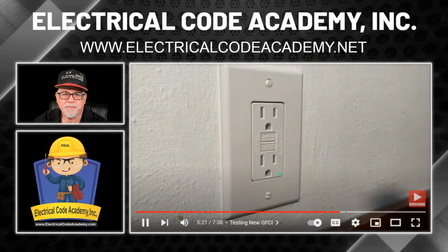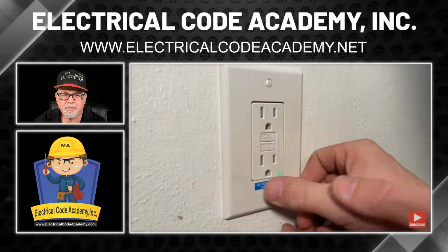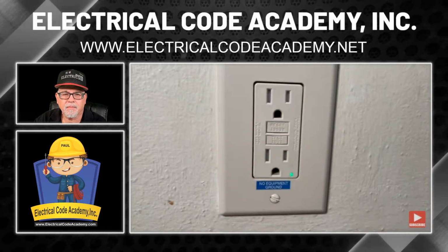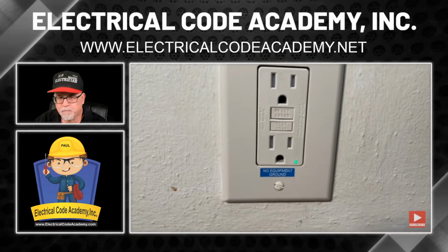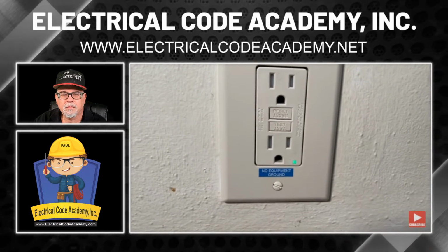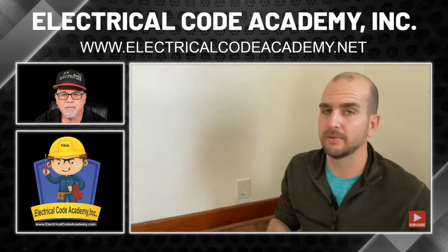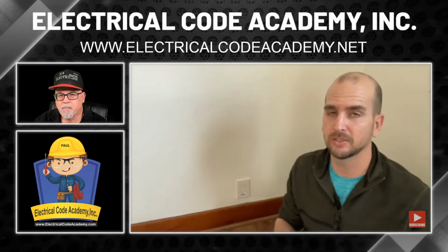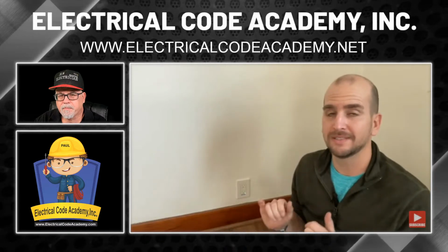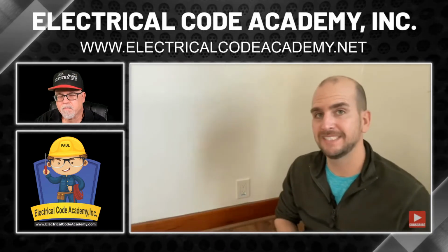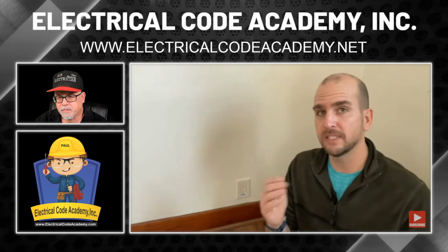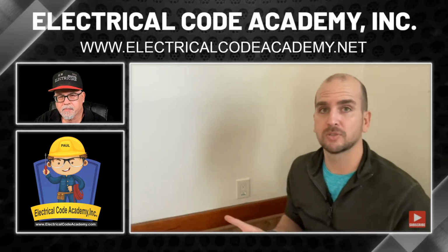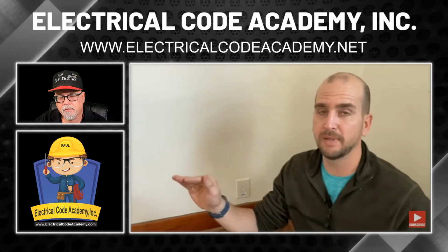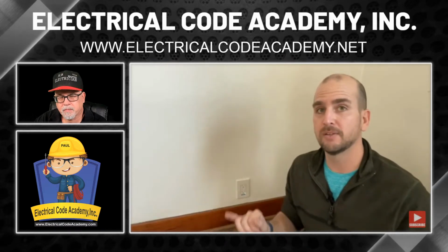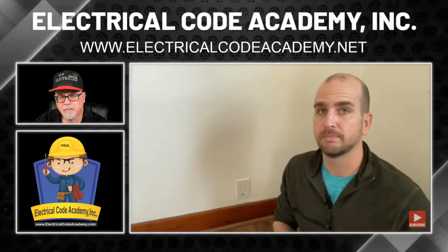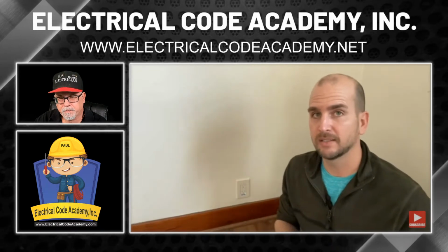Because of that, NEC does call out that we need to label a no equipment ground sticker on the faceplate, and the sticker will be found in the GFCI box so you can use it. So not too bad, right? Something you can knock out pretty quickly, and it's so much more functional and safe to have this GFCI 3-prong. If there is a fault there, this will actually trip. It doesn't have the ground return path, which is ideal, but if there is a fault, it will trip because of the design of the GFCI outlets.